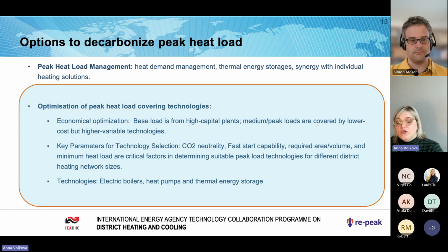From an economical point of view, it's acceptable to have lower capital costs but higher operation costs compared to base heat load covering technologies, where it's preferable that operation costs be lower. Key parameters for technology selection are CO2 neutrality, fast start capability, required size—area, volume, or borehole depth—and minimum heat load, which are critical when determining suitable peak heat load covering technologies.